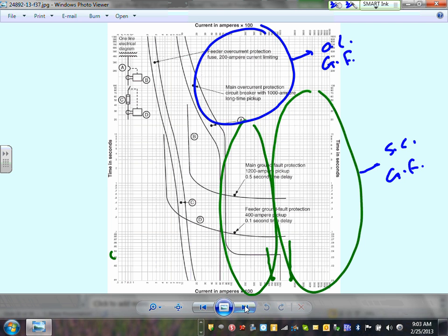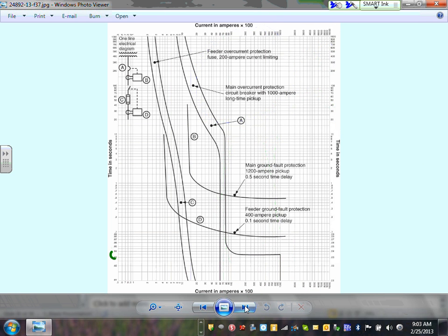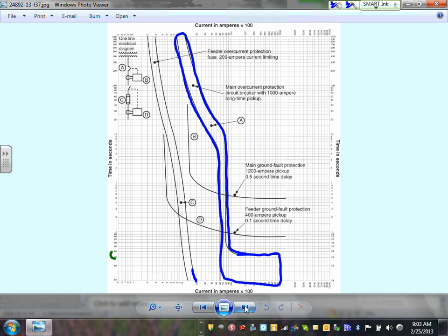When I start coordinating with you guys, that's what we're going to be doing. The last thing I want to do is coordinating the ground fault. This is very important, guys, because it has two coordinations. Like hospitals, it has the overcurrent protection coordination here. That's my main coming back, and I have another fuse that coordinates with it. These two coordinate with each other. This is for overload, and then I have a ground fault. Can you see the ground fault fully coordinated with the ground fault?